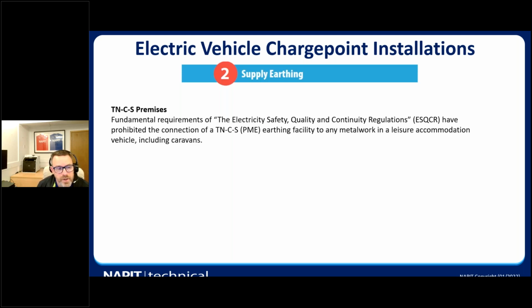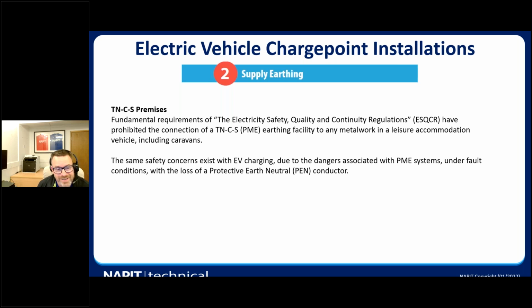So TN-C-S premises, the fundamental requirements of the Electricity Safety, Quality and Continuity Regulations, ESQCR for short, have prohibited the connection of TN-C-S systems to metalwork of leisure accommodation, including caravans, and the same concerns exist with EV charging due to dangers associated with the PME system under fault conditions when we lose the PEN conductor.